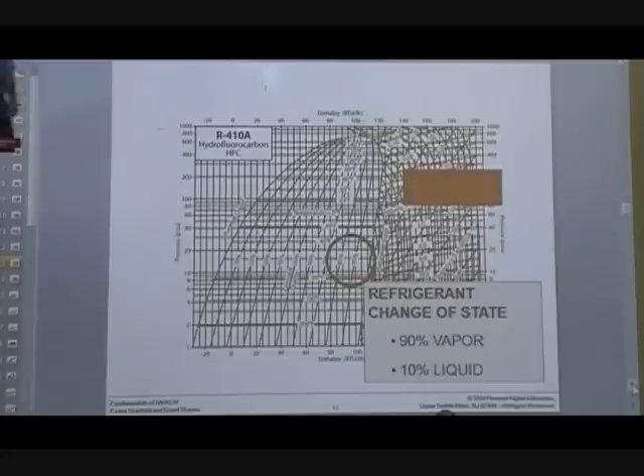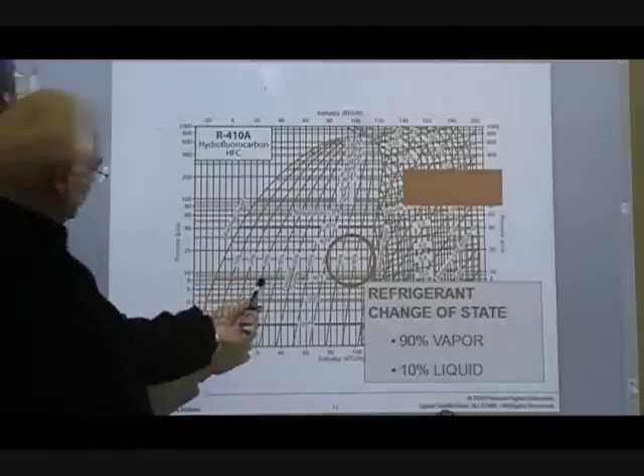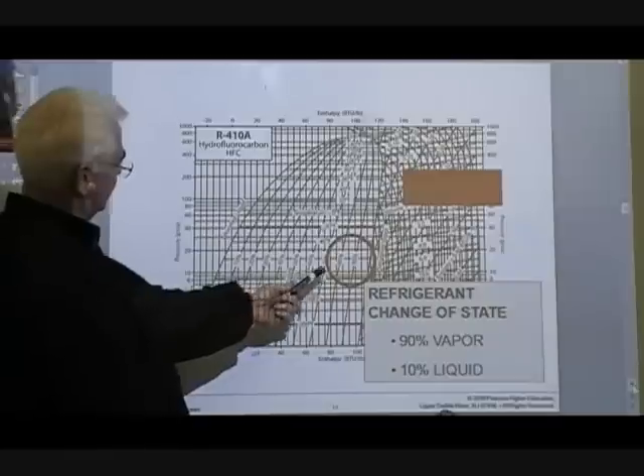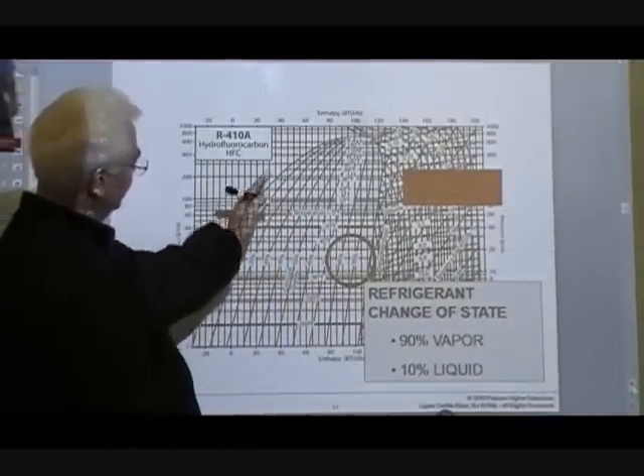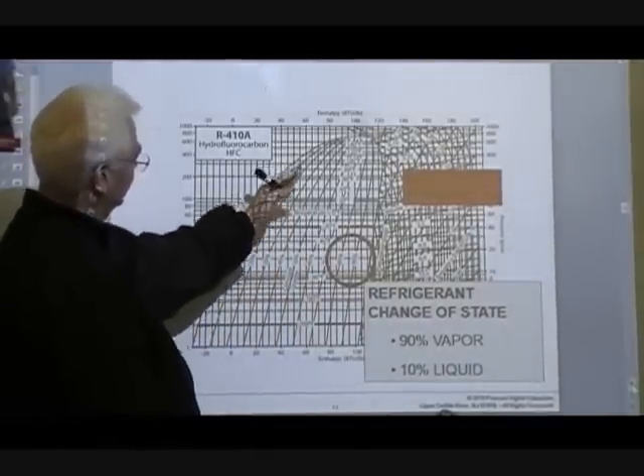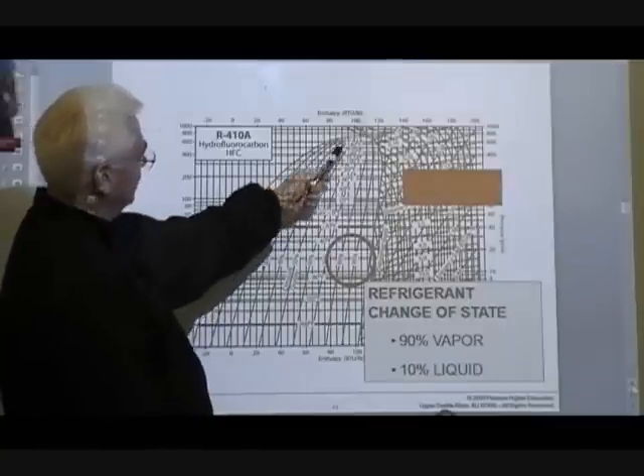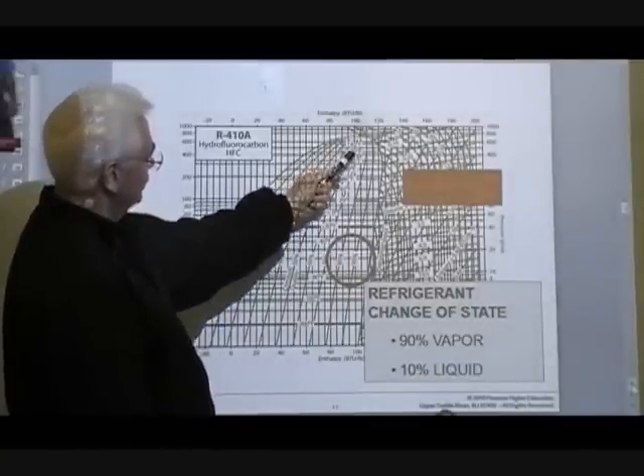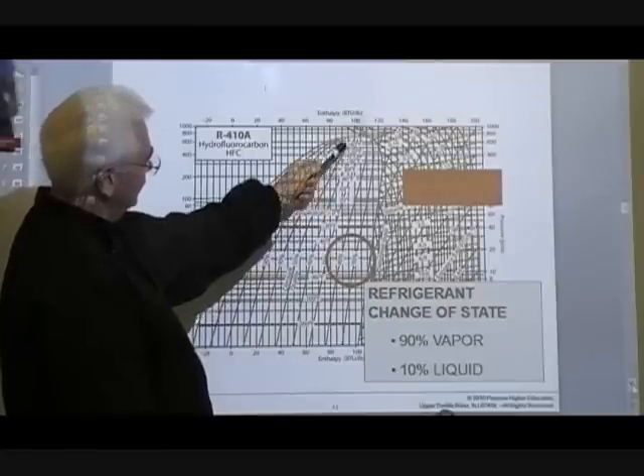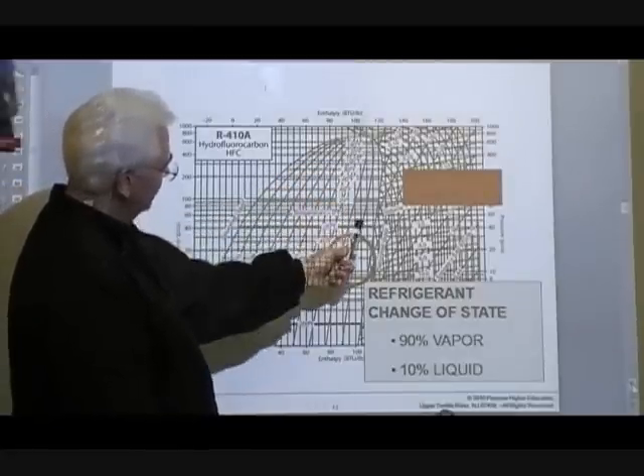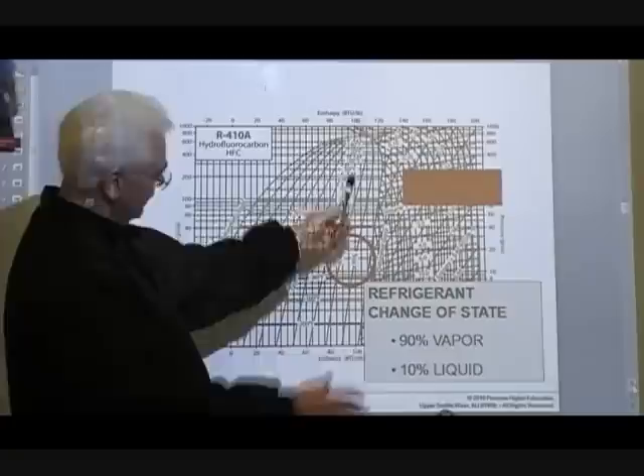You want 100 percent vapor exiting that evaporator. The refrigerant over here on this side of the chart is rejecting heat in the condenser. You come up here to the peak — your peak discharge pressure — and then as it goes through your metering device, somewhere right in here, depending on whether you have a 40-degree evaporator, this is where the refrigerant is going in, entering the metering device and the evaporator.